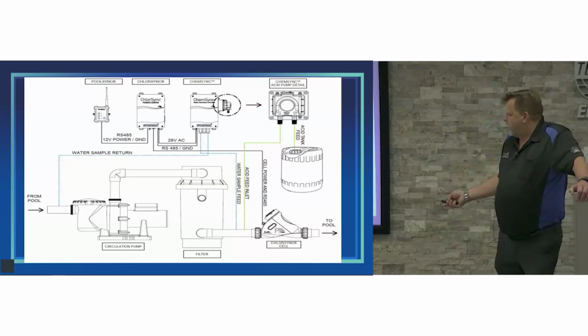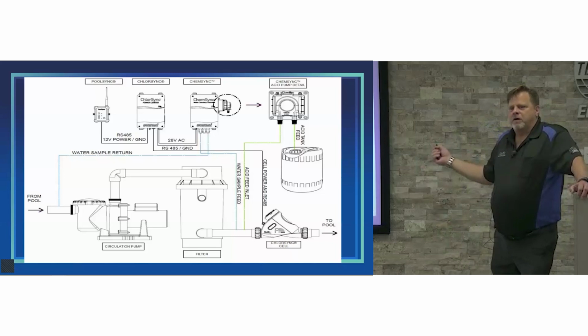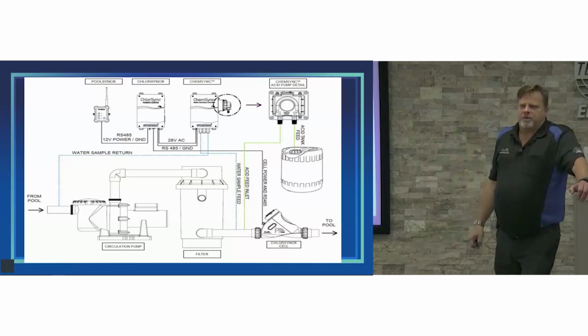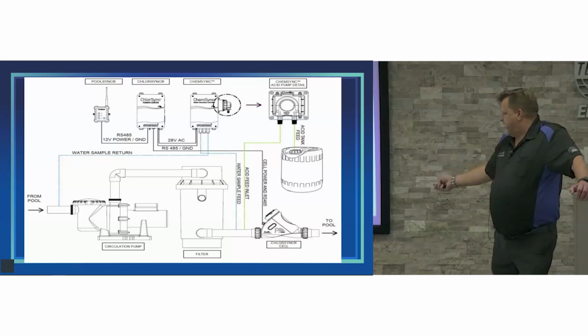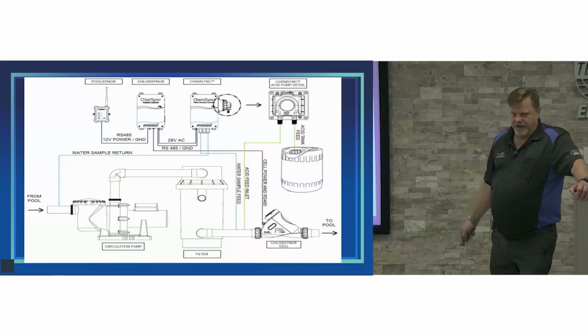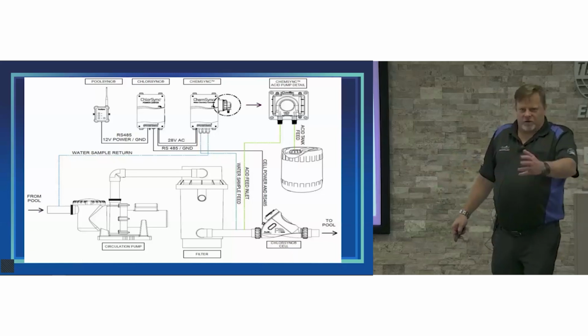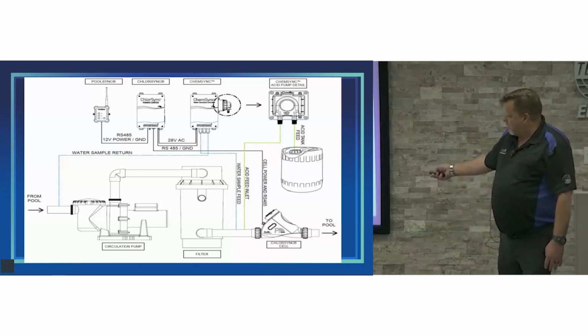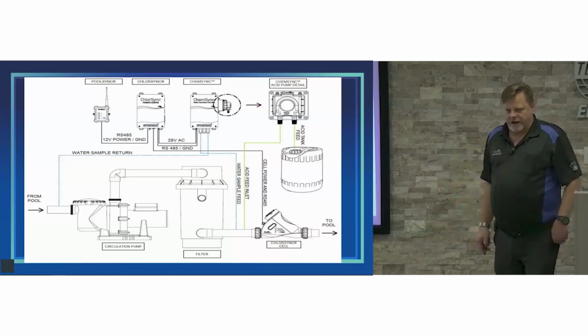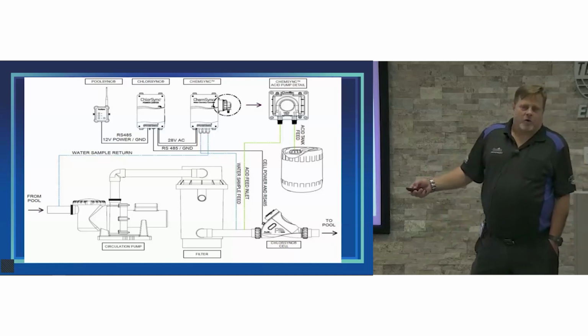If you look right here, we have the water feed tube going up, and then we have the acid feed tube. So we're sucking water to be tested here, and we're feeding acid here. The acid is downstream of where we're taking water up to be sampled, so the acid being fed won't interfere with your reading. If I was taking it downstream of the acid feed, like on this side, then yes, my readings would be interfered with by the acid being fed, and you would have it cycling on, cycling off, cycling on, cycling off. But because you're taking the water sample before the acid feed tube, it plays no factor in the reading, and it will help keep the cell clean.